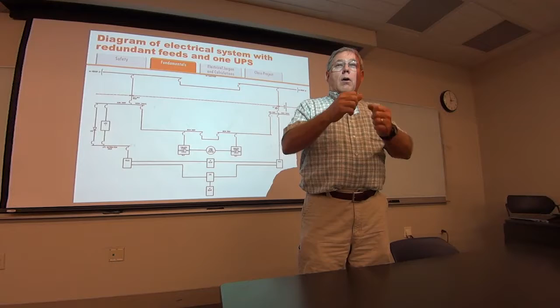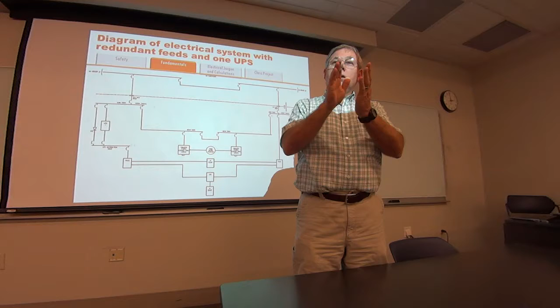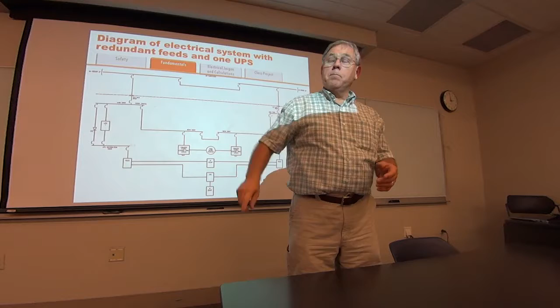Surge protection would be for something like where you have lightning strikes, or where you're switching capacitors on the line and you get a little ring, or where you're opening vacuum bottles, which open very quickly and they extinguish the current, and the magnetic field can't collapse immediately in the wires and all the systems out there, so it does something like that. And it's not that big a problem these days.